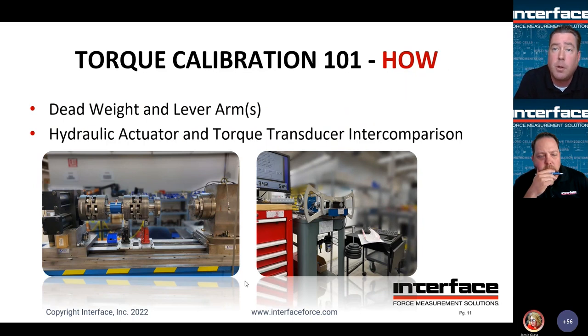For torque calibration, torque is loosely defined as force at a given length. So we accomplish this in two different methods. Number one, we have dead weight and lever arms. We have an example here on the right-hand side of the slide. This is an air bearing type stand where we have a shaft suspended by two air bearings, and there is a lever arm assembly that is attached to said shaft. It's tough to see there, but there are two nylon cups on the other side, and that is where the torque transducer would be fixtured in. And then you can see we have a dead weight stack applied to the end of the lever arm, applying a calibration mass.